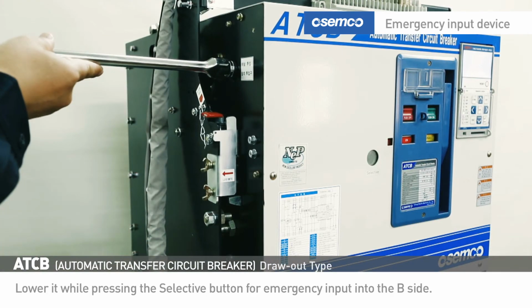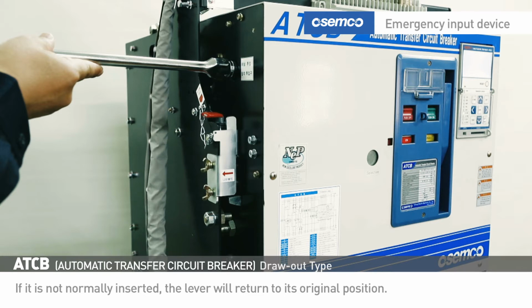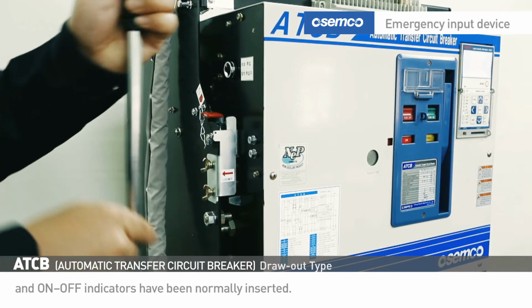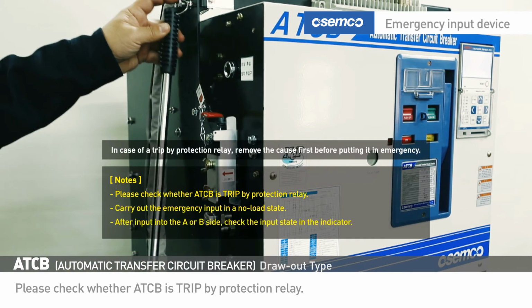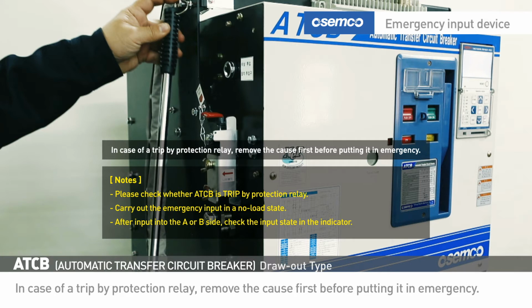Lower it while pressing the selective button for emergency input into the B side. If it is not normally inserted, the lever will return to its original position. After completion of the input, check whether the transfer state and on-off indicators have been normally inserted. Please check whether ATCB is trip by protection relay. Carry out the emergency input in a no-load state. After input into the A or B side, check the input state in the indicator. In case of a trip by protection relay, remove the cause first before putting it in emergency.